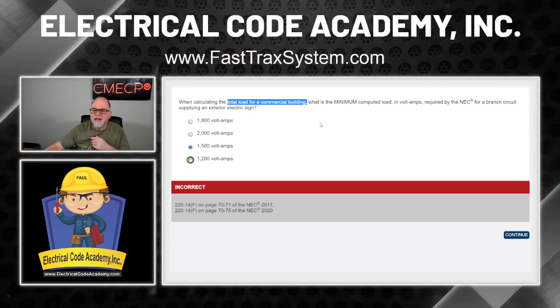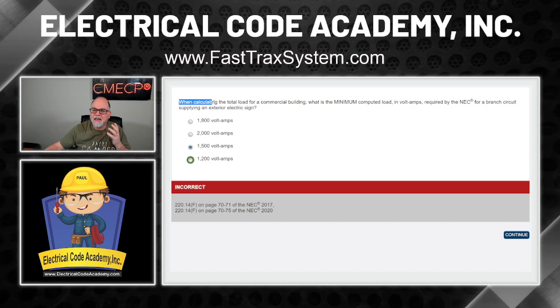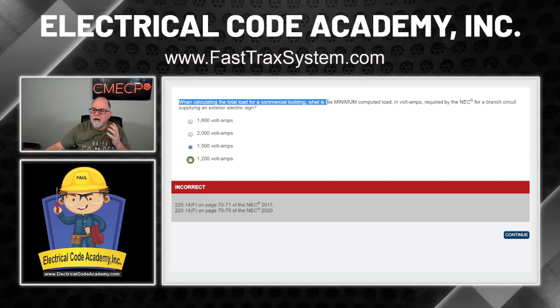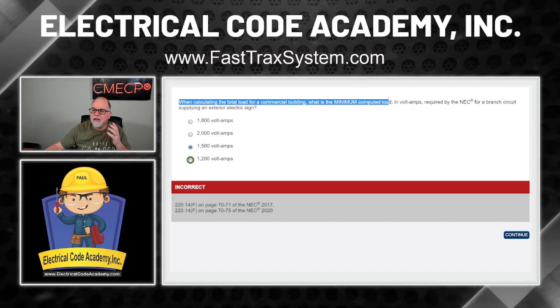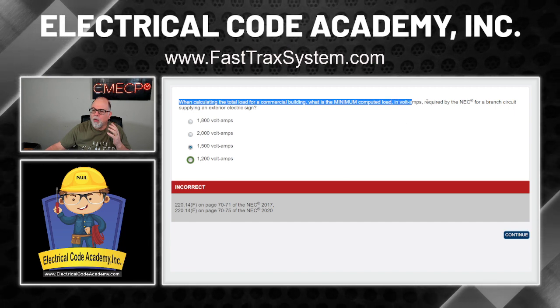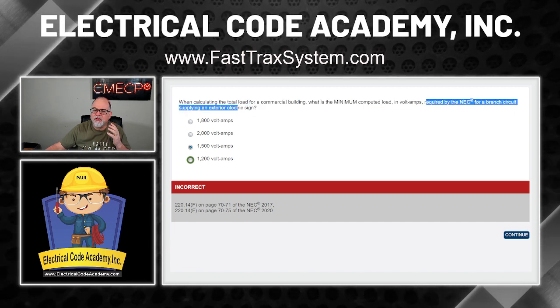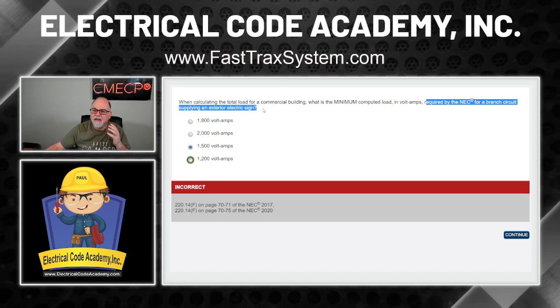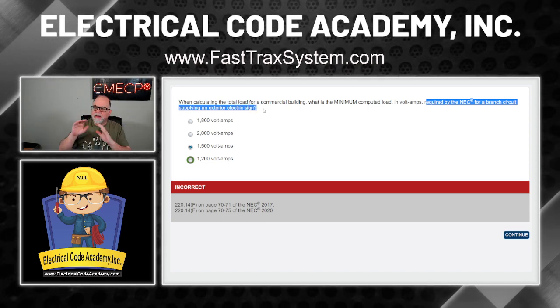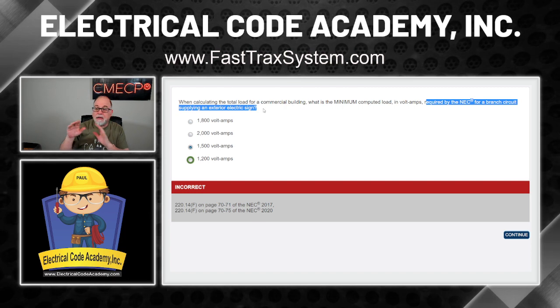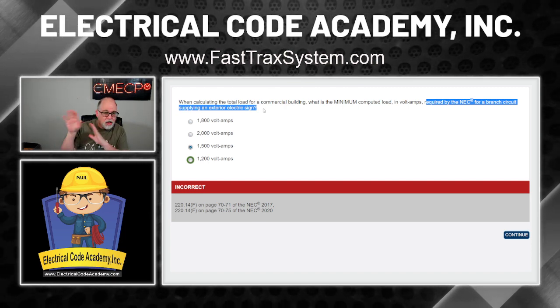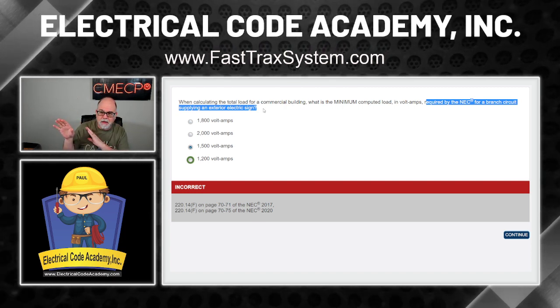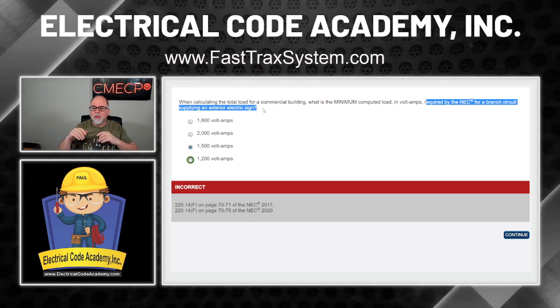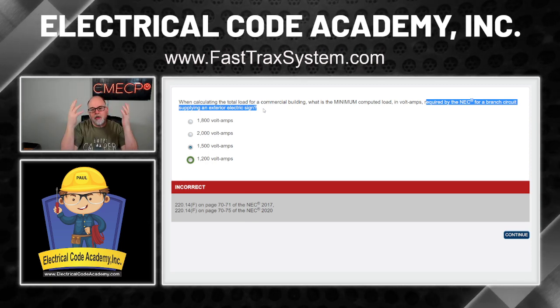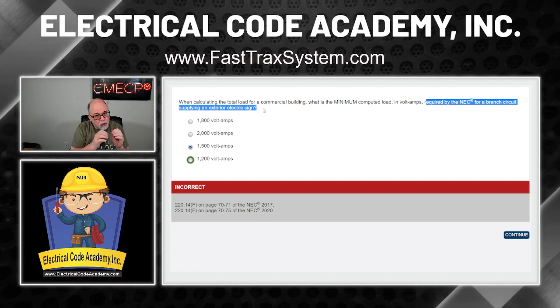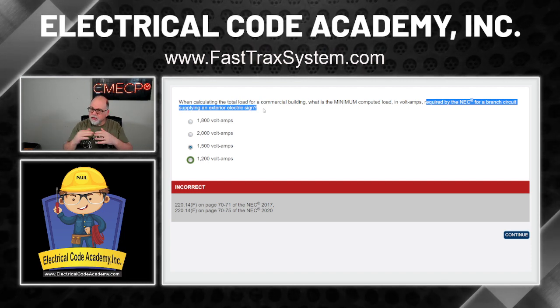Because this question misled you. It says, when calculating the total load of a commercial building, what is the minimum computed load in VA required by the NEC for a branch circuit supplying exterior electric sign? Didn't matter because it wasn't sizing the branch circuit. It was obviously a branch circuit is the load to the exterior sign, but we're doing a load calc, an overall load calc. That's why we have to focus on 220. You with me? You see how that works?